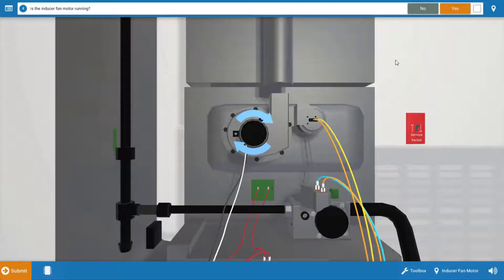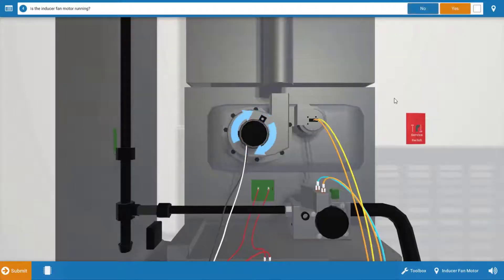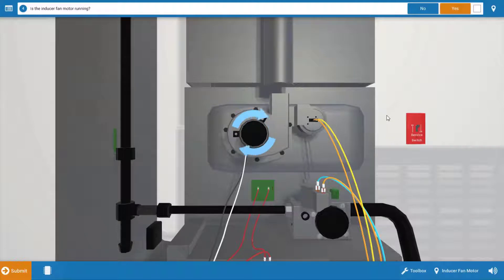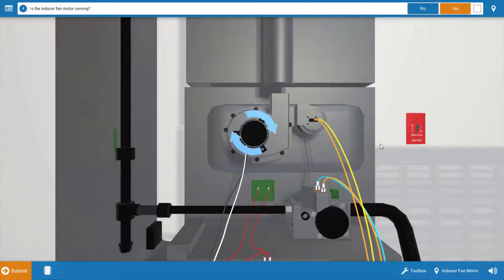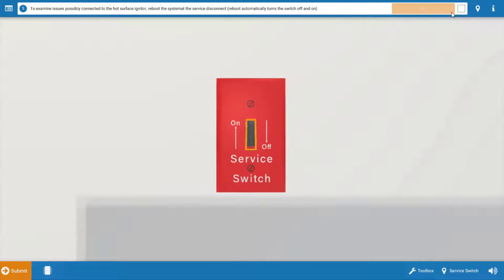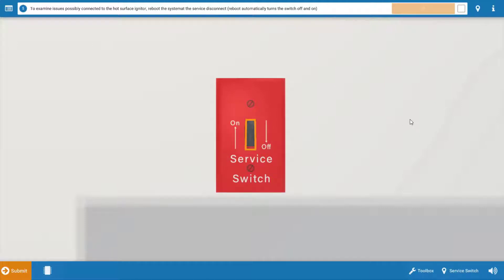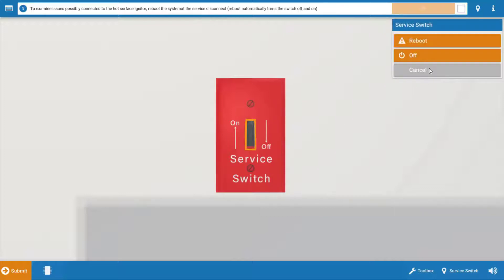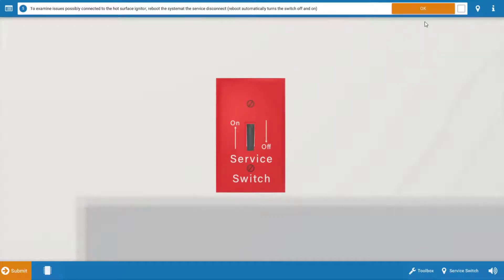Click OK, and next we want to look at the inducer. That's the first load that's going to come on in a normal sequence of operations, and that is running so we can click yes. Next, it may be necessary to reboot or restart the system so that you can observe one full cycle of operation in the normal sequence. So click on the service switch, which will just turn it off and back on. Click reboot. Once we do this, click OK and be ready to see what comes on.